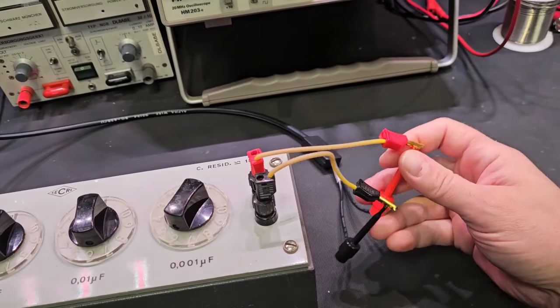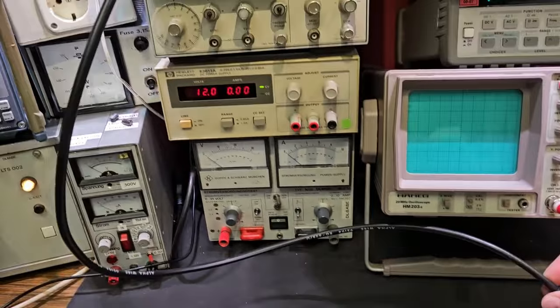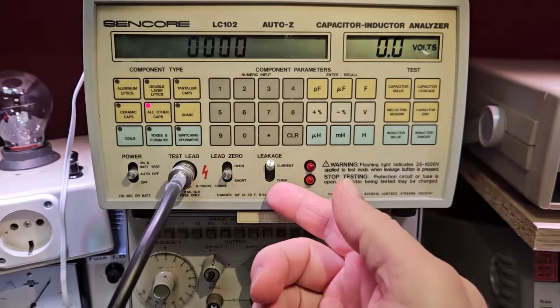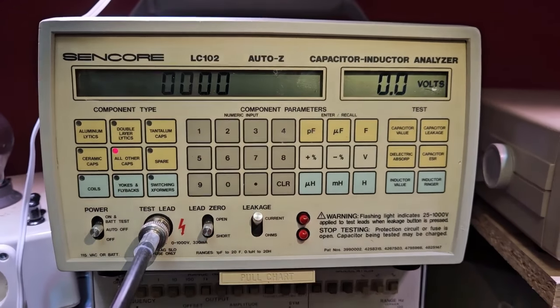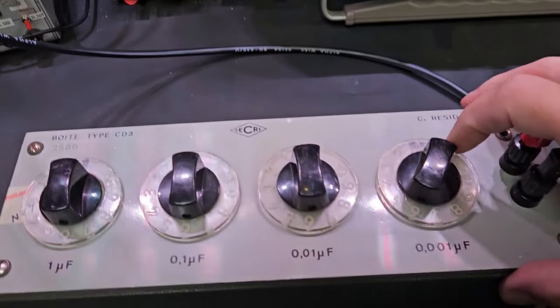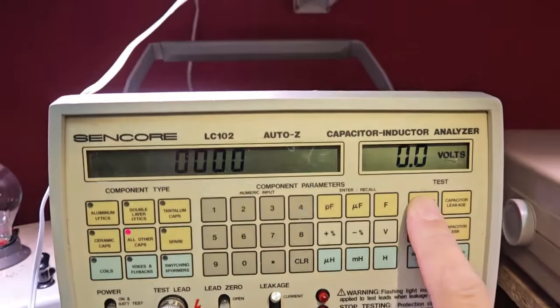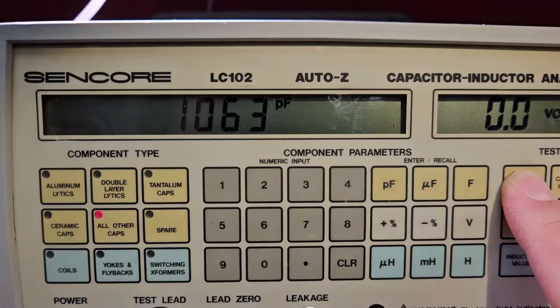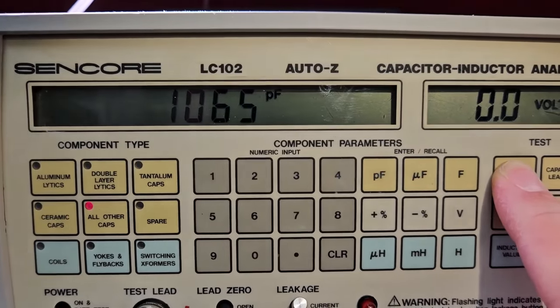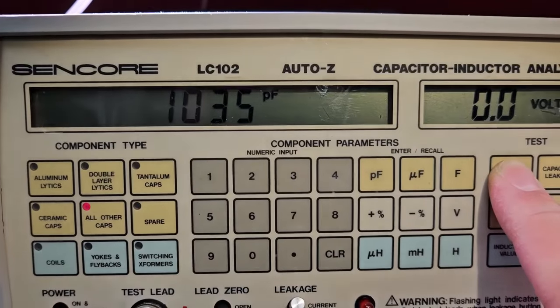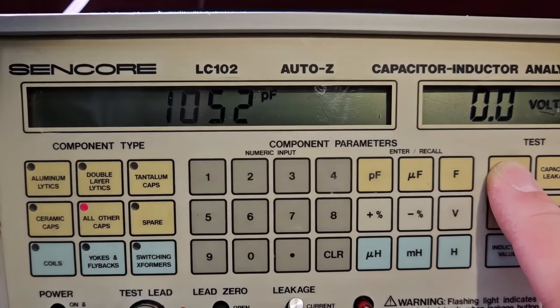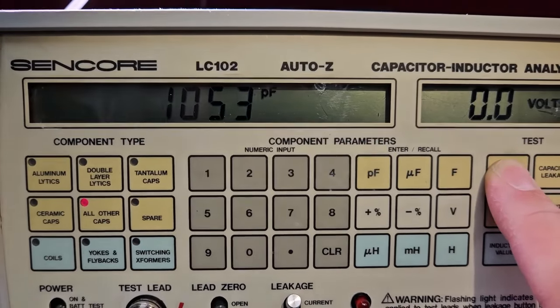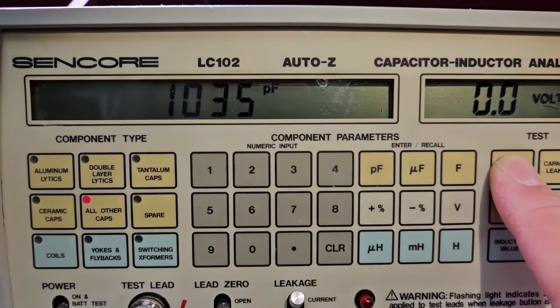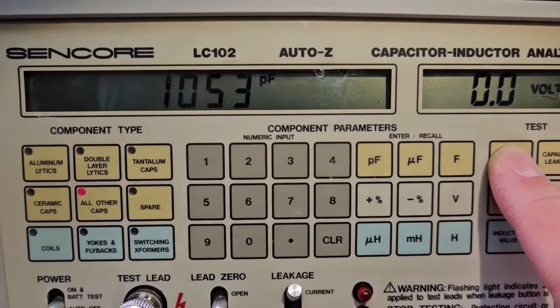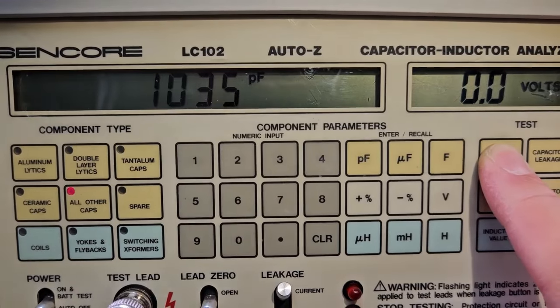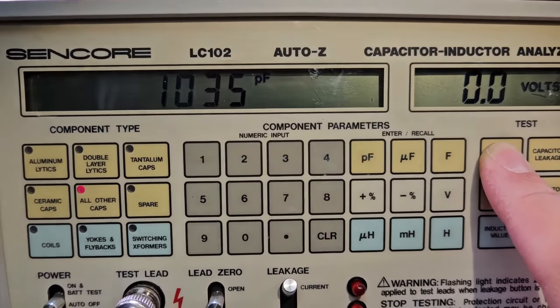I attached it to a normal standard Sencore test lead. I did the lead zero calibration with open and short. And so I selected 1 nanofarad here, and if I press the capacitor value, look how much this one is shaking, or how it's not stable. It's gambling around so many picofarads that it's really impossible for me to align it to a precision of 5 picofarads. It's varying more than 10 times the precision I need for the alignment.